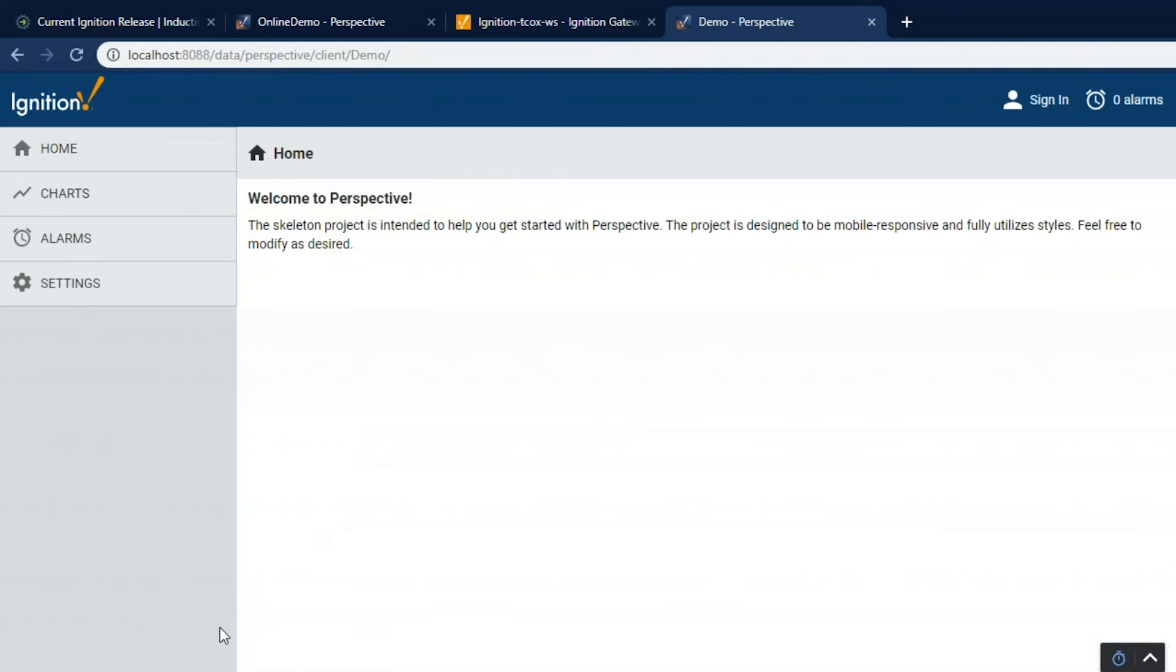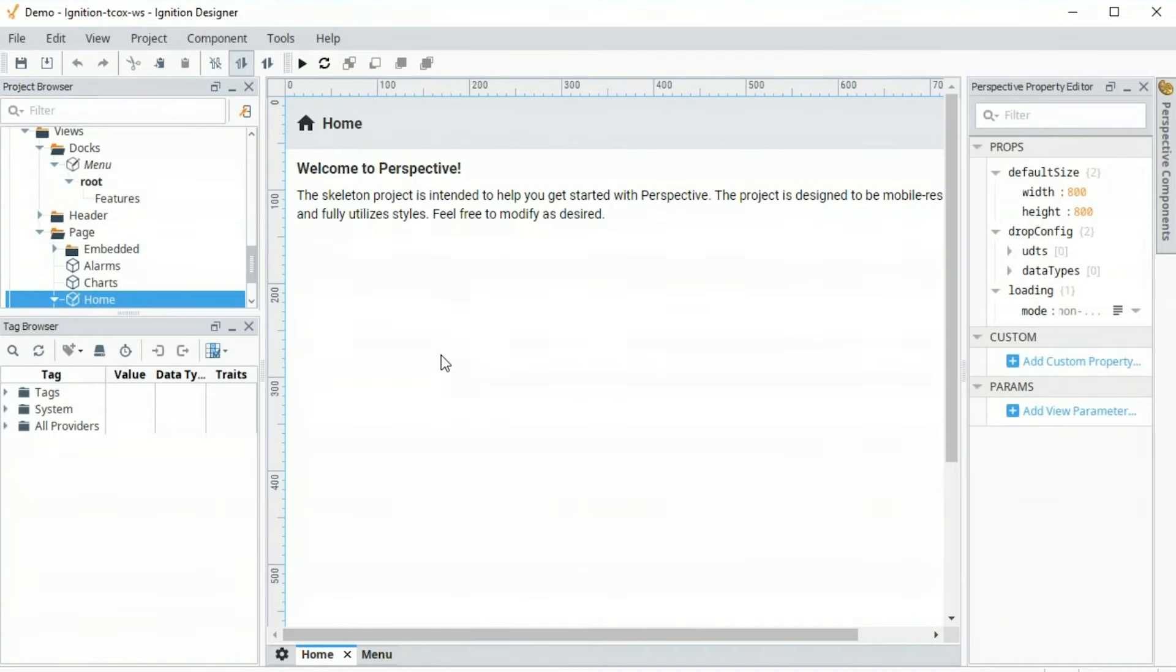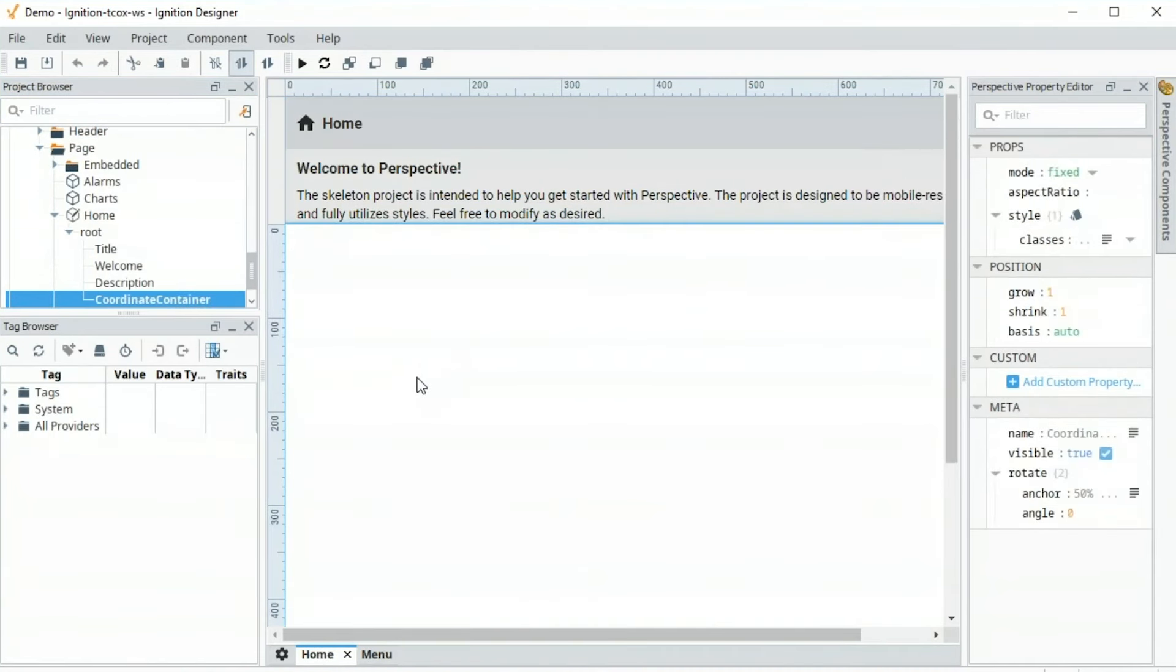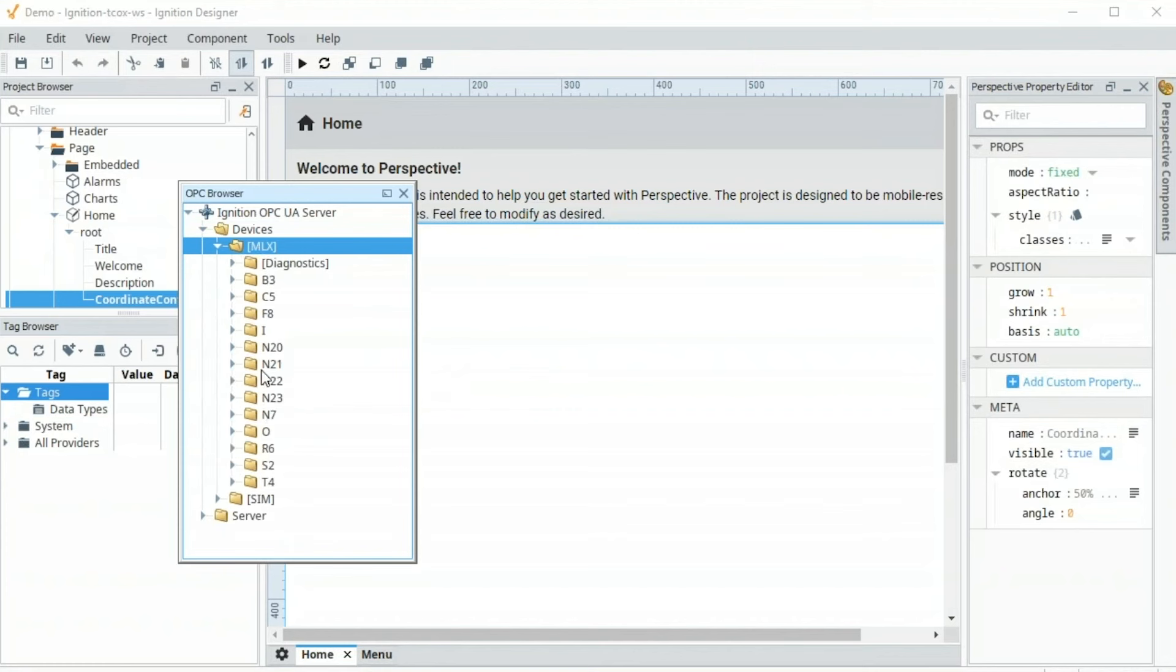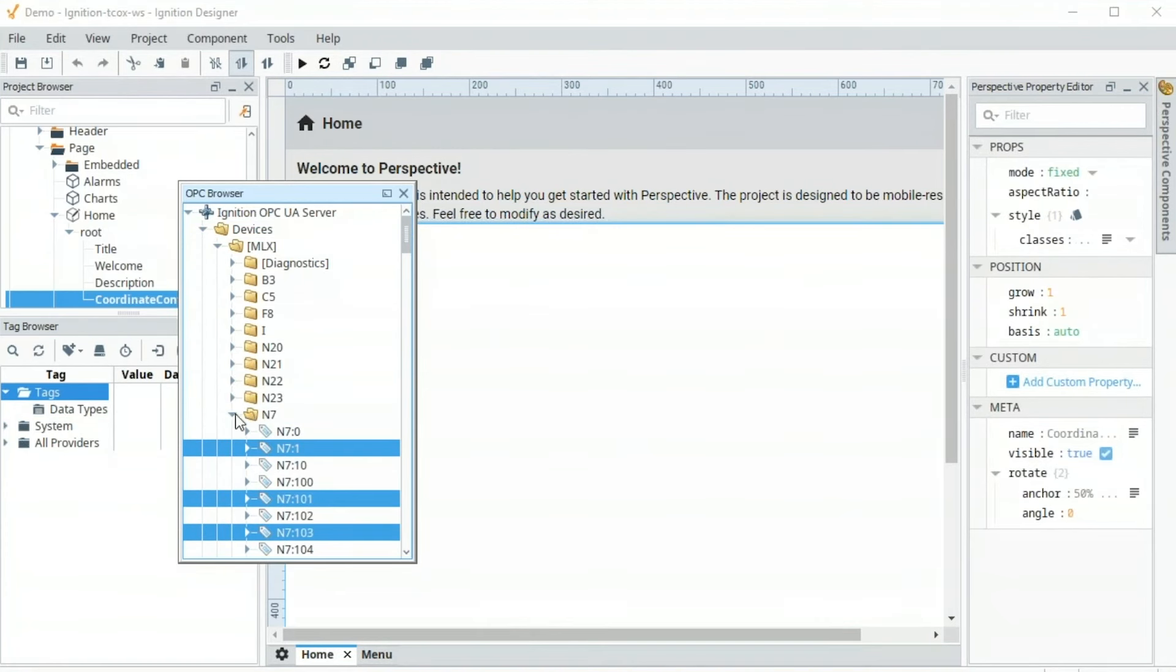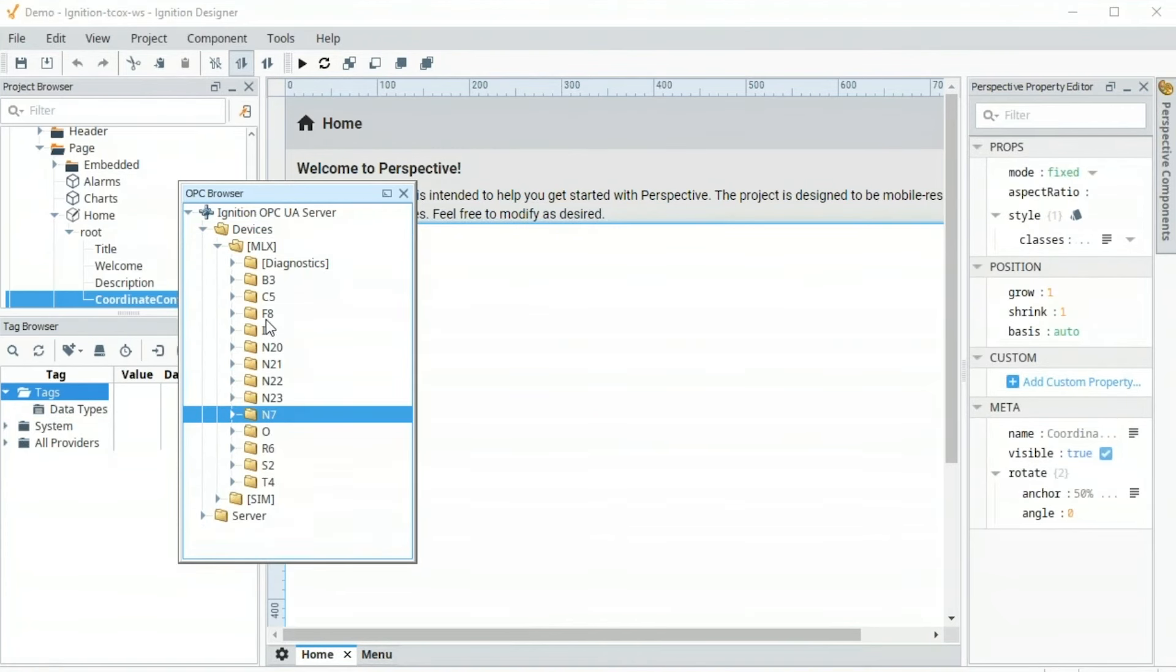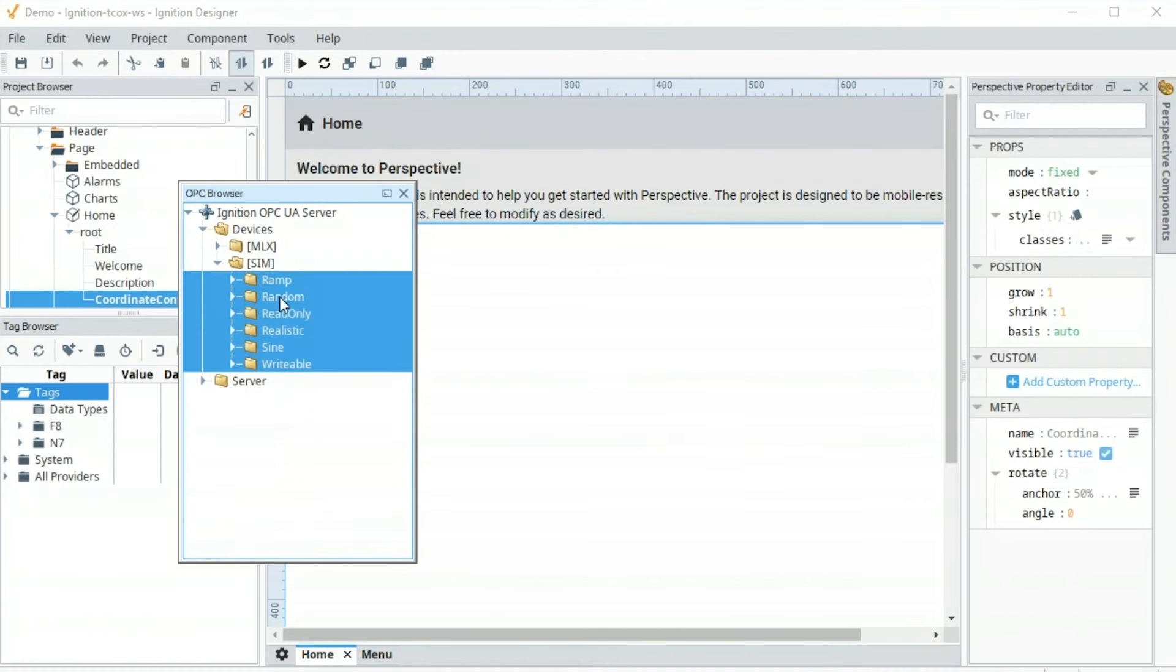What I want to do now is actually build out a real screen, bring in some tags, do some real-time status control and history. So let's go back to the designer, back to the home screen. And in order to do any configuration, we've got to have tags. So over here is our tag browser. I can go and browse our OPC server. There's the MicroLogix with all of its tags that we can bring in. I can select individual tags I'm interested in or entire folders. So I'll select the N7F8 folders, drag them in. We'll go to the simulator and drag all of those folders in as well.